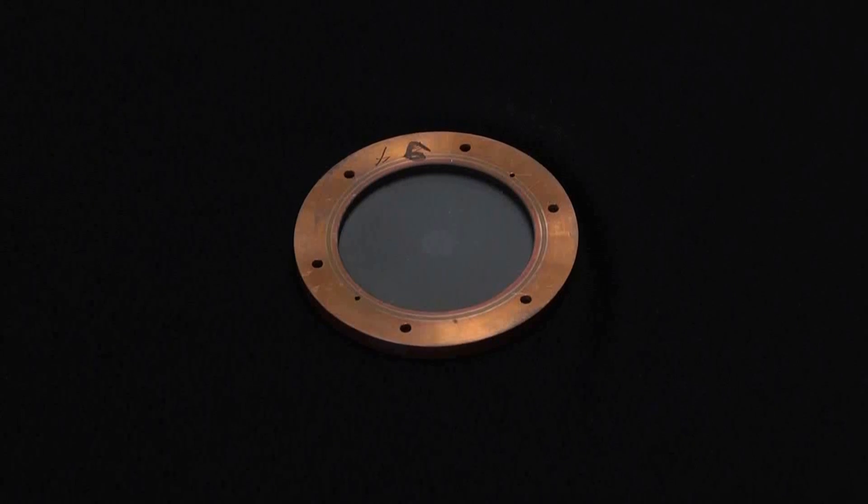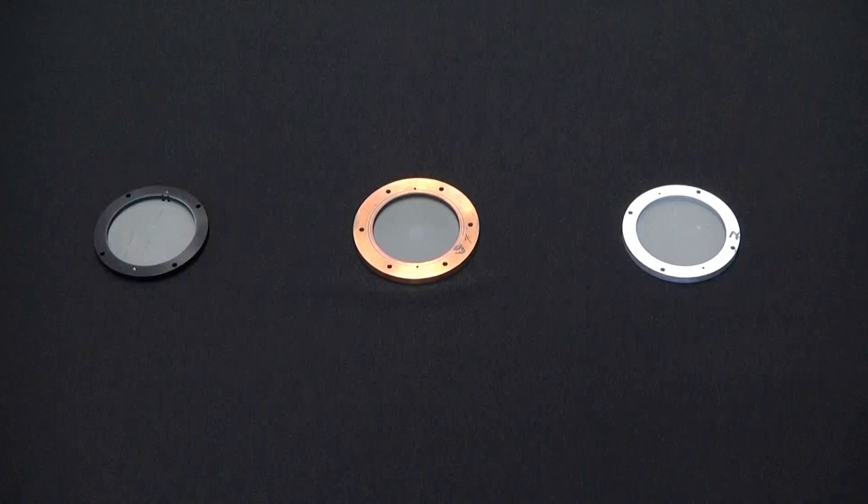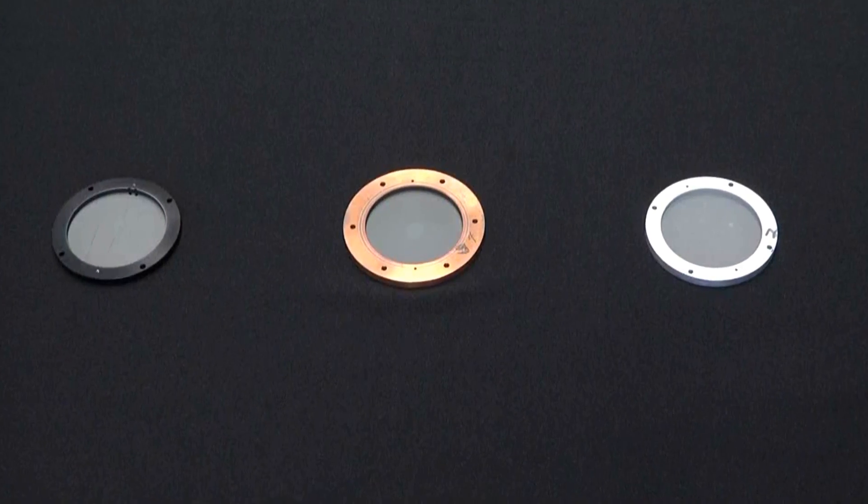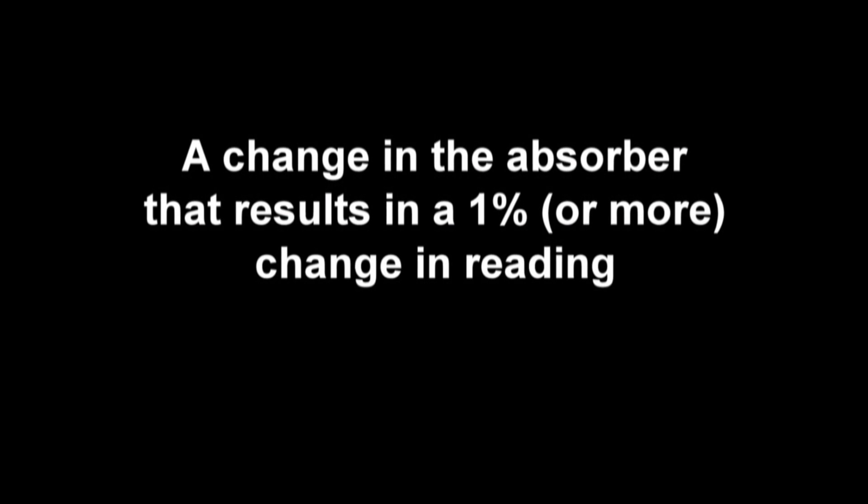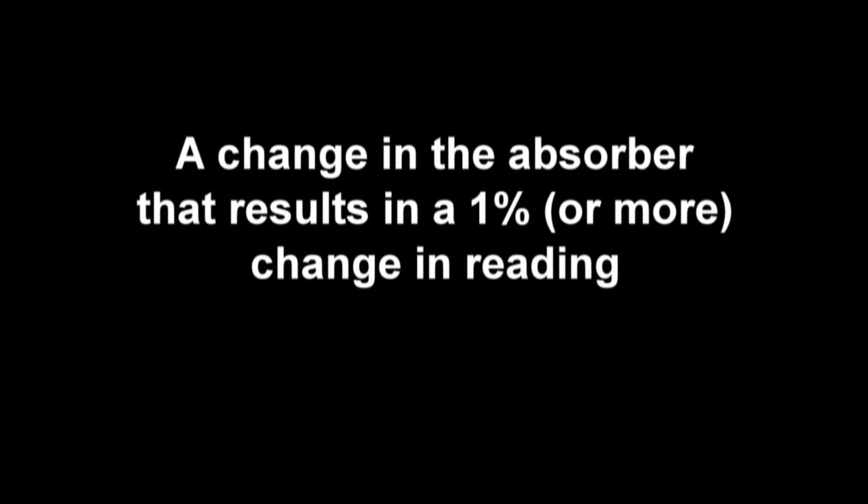Here we can see an even subtler example. How do we decide if these cases are damaged or not? We generally define damage as a change in the absorber that results in a 1% or more change in reading.